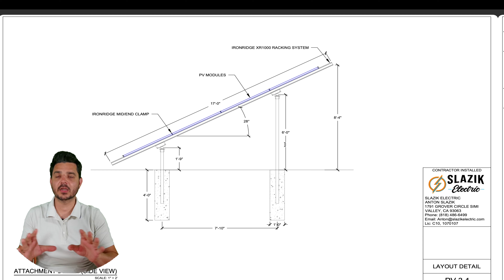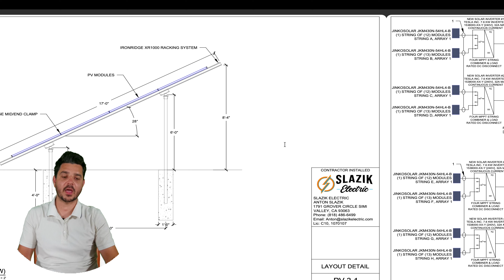You've got 4 modules on each rail, very clean, very simple, and we're just going to match it to the existing post. So the height and everything is going to be comparable to what's already on site, so we can just go boom and slap on the array accordingly. Now, getting to the single line diagram, this is where things get complicated because it's 2 systems on one site, right? So again, there's not a 400 amp automatic transfer switch. There's no 400 amp Franklin aGate.